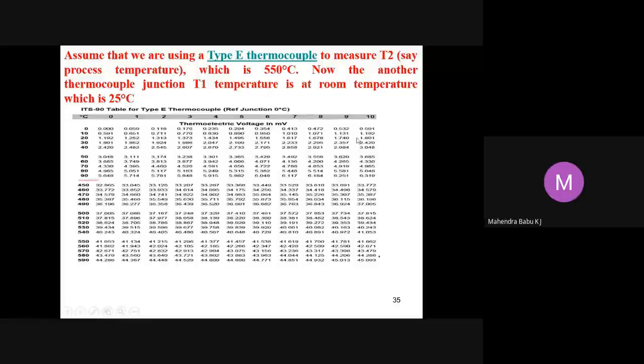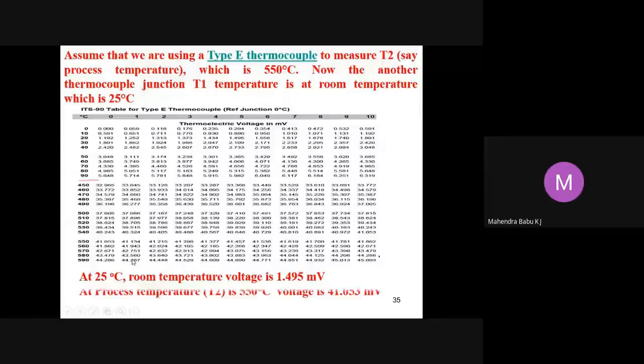So this is the table corresponding to the E-type thermocouple. To get the voltage at 25 degrees Celsius, go to 20 degrees Celsius, then move to the right side and take the reading below the fifth column, that is 1.495 millivolts. That is the room temperature voltage in millivolts: at 25 degrees Celsius, the voltage is 1.495 millivolts. And at the process temperature of 550 degrees Celsius, we directly get a voltage of 41.053 millivolts. So you can note these two down directly from the table.